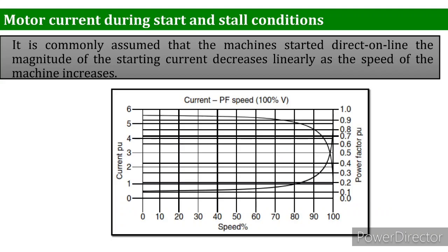The next issue we have is the motor current during start and stall conditions. The magnitude and the permissible duration of the motor starting currents are the major factors to be considered in the application of overload protection. We will discuss these also in our next issue. But now it is commonly assumed that the machine is started DOL, direct online.